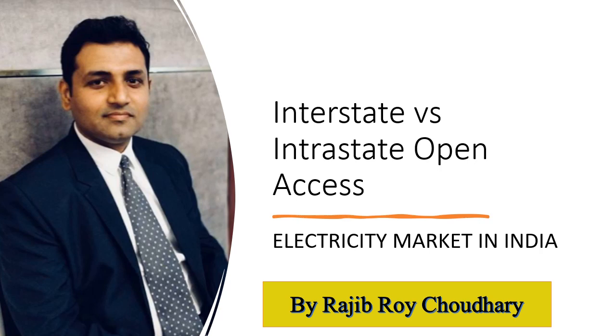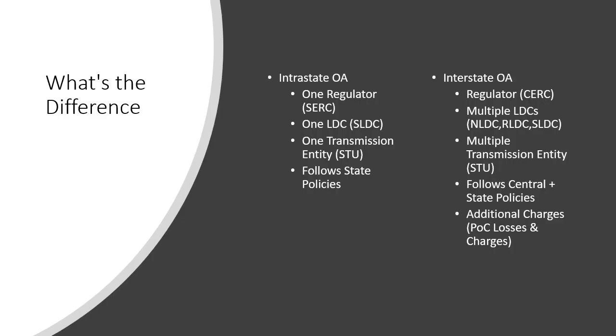For those who have seen earlier videos on open access, the major difference is between intrastate and interstate open access. Intrastate open access means the generator supplying power and the consumer consuming power are both within the same state. Under intrastate open access, you are dealing with only one regulator — the State Electricity Regulatory Commission — so all policies, disputes, or arbitration between generator and consumer go to that single regulatory commission.